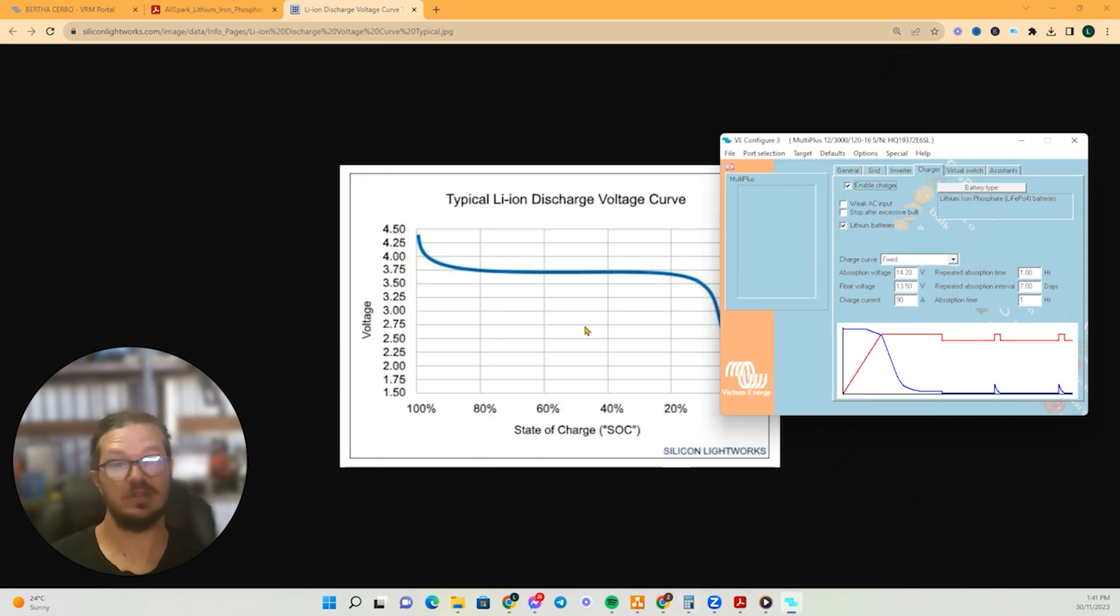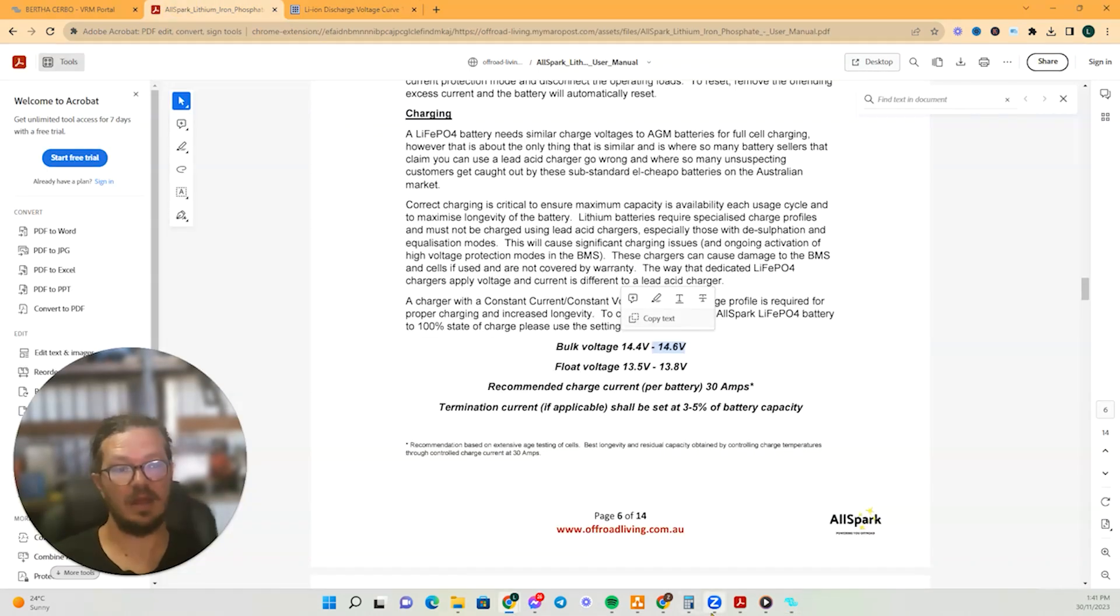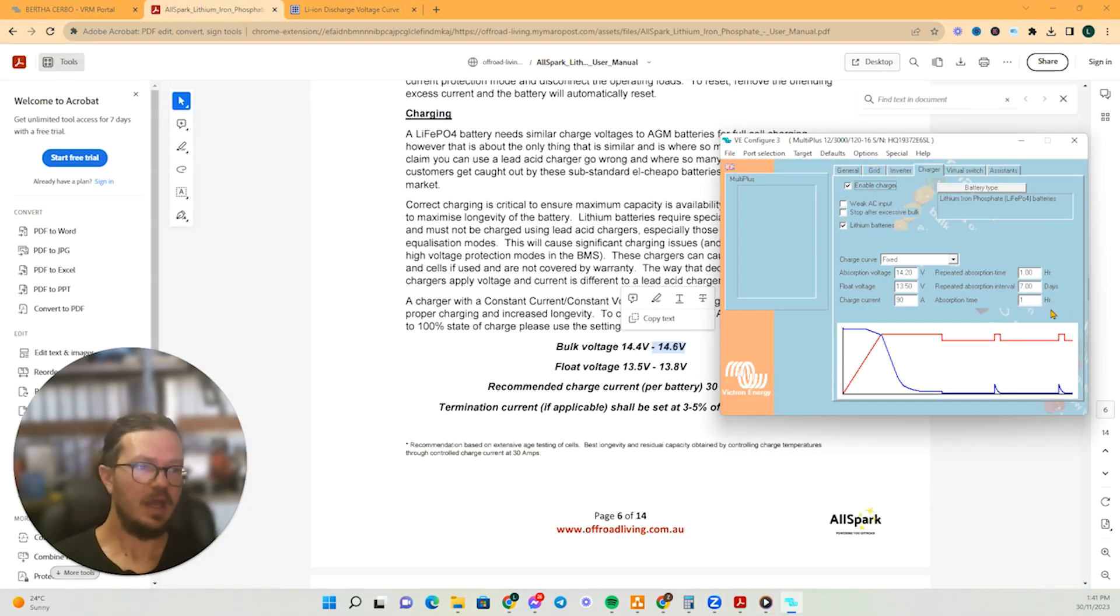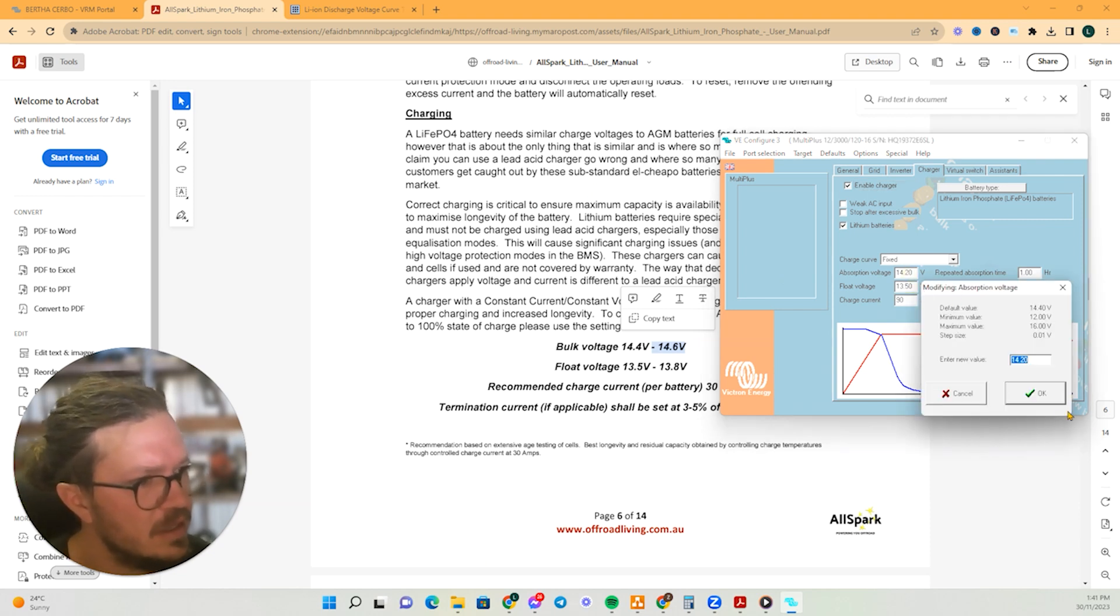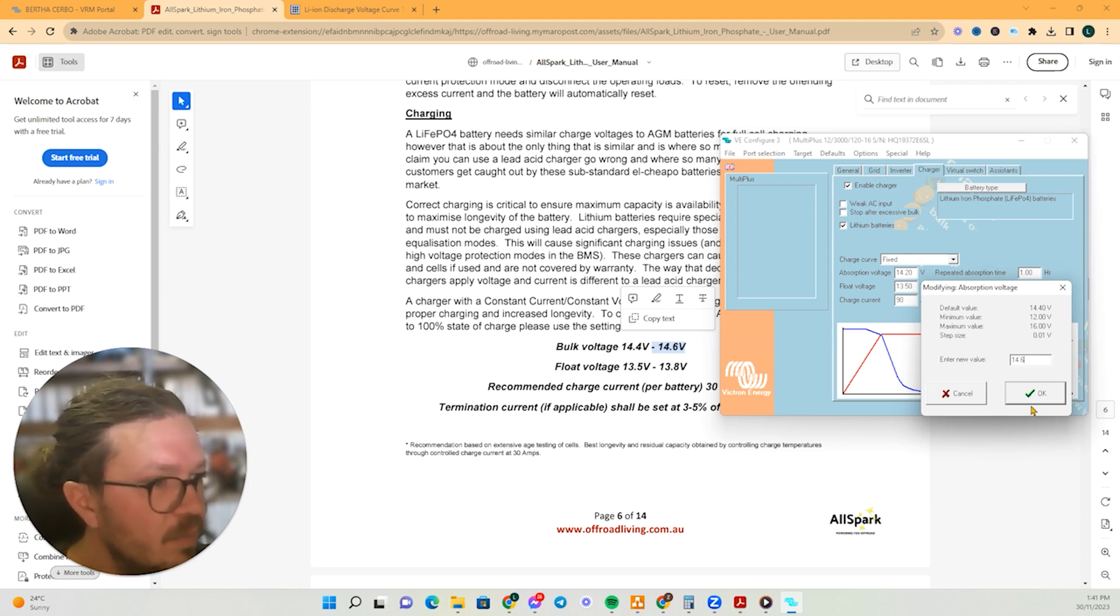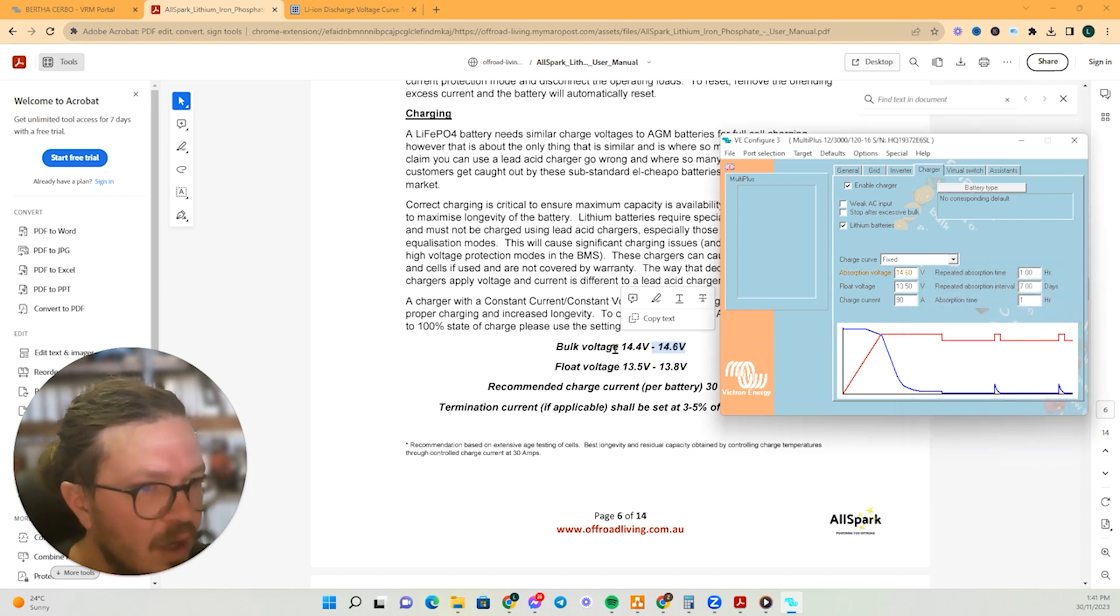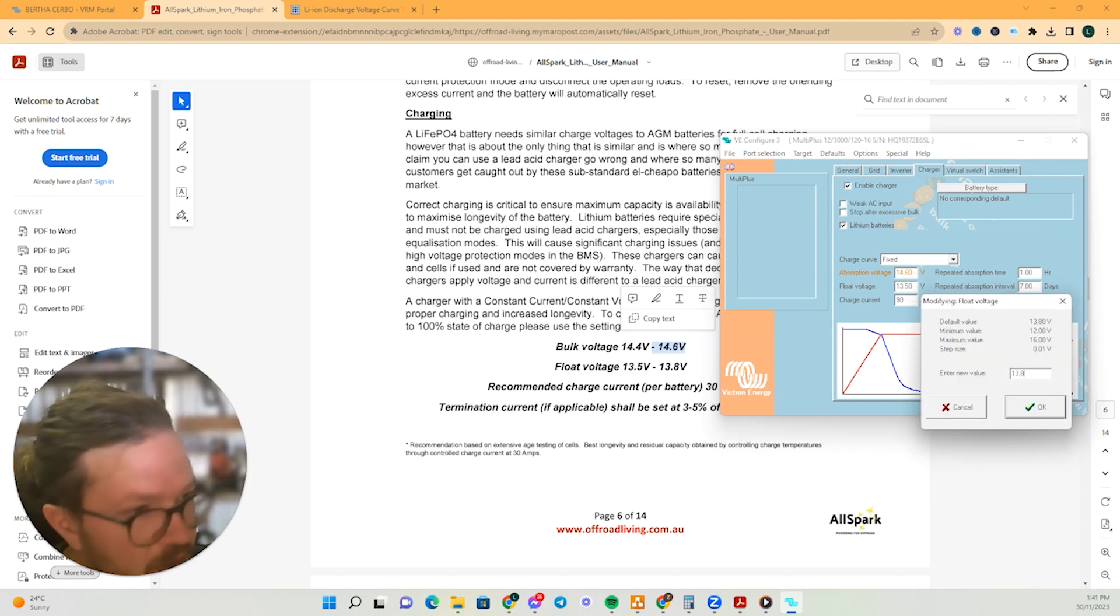So which is not ideal, but and the batteries might not be hitting that real happy stage as well. So something that I'm helping him out with is to change this absorption voltage, so that one will be 14.6. We'll go on the higher end of that. And then the float voltage will go, we'll go to 13.8.